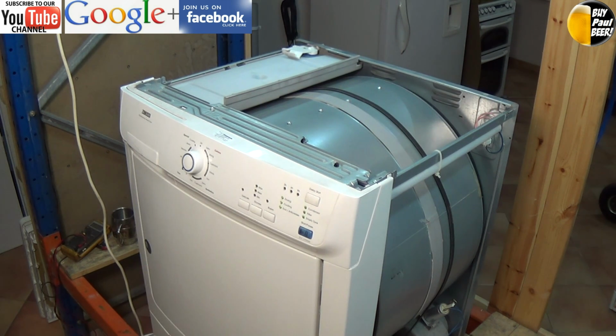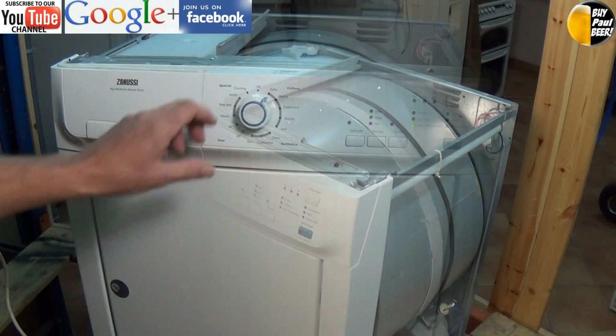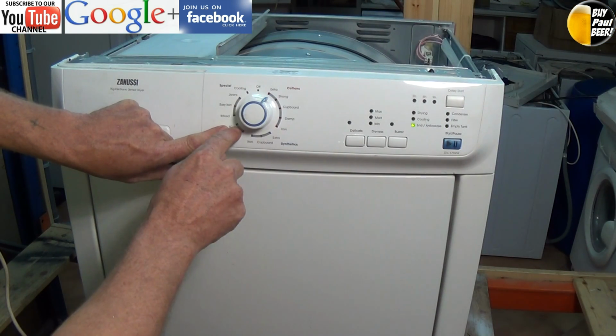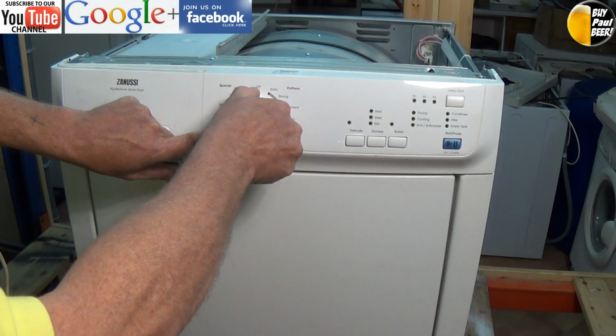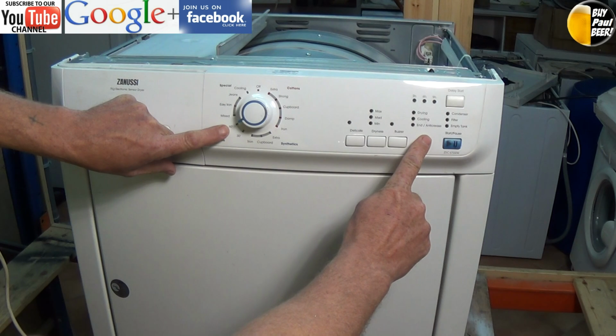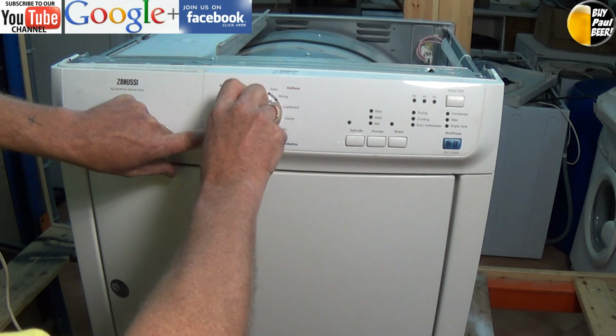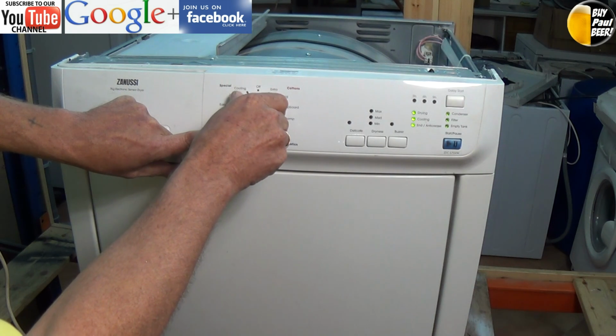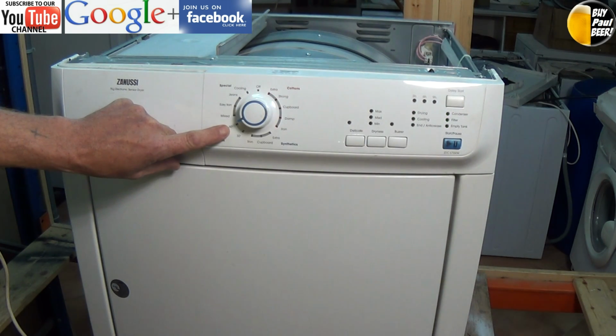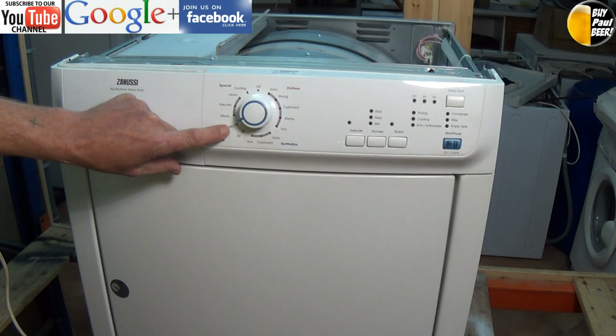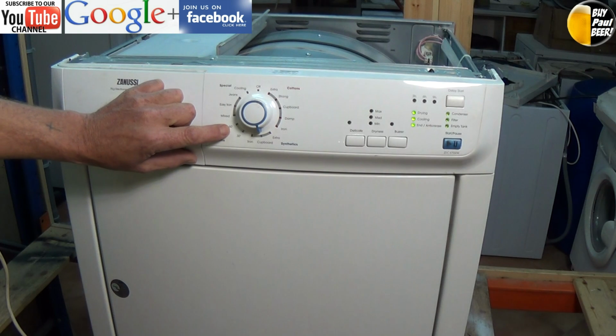And the last test is to clear the memory in the RAM, and this will wipe out any error codes that actually exist in the machine. And what you have to do for this is very carefully start at number 1 in test mode sequence, and without stopping. It's very important not to stop on position 7, otherwise you will create an error code. So just quickly turning the dial all the way through to position 10, and if there's any error code there, it would have been stored.